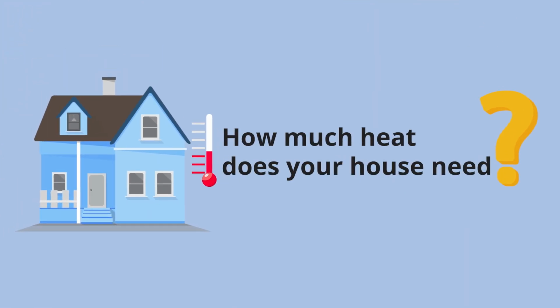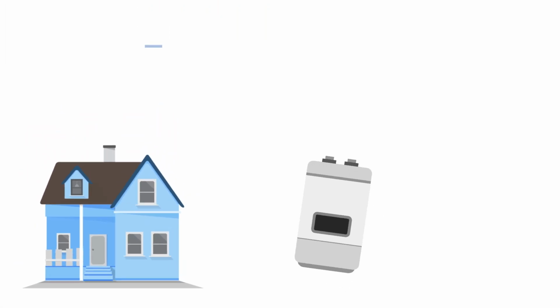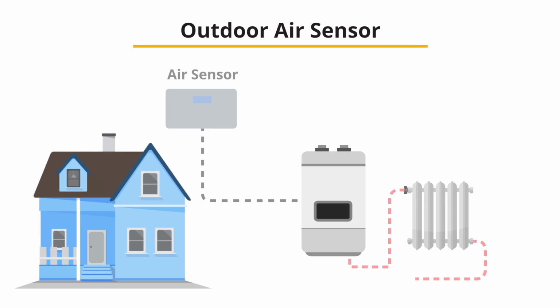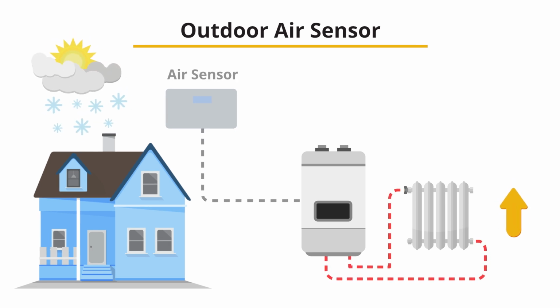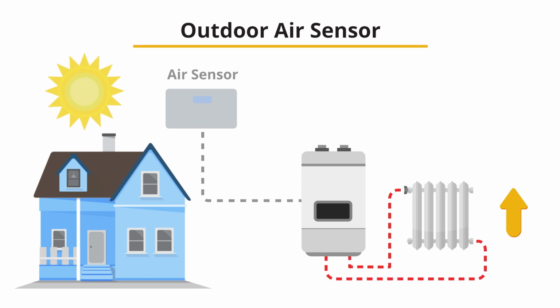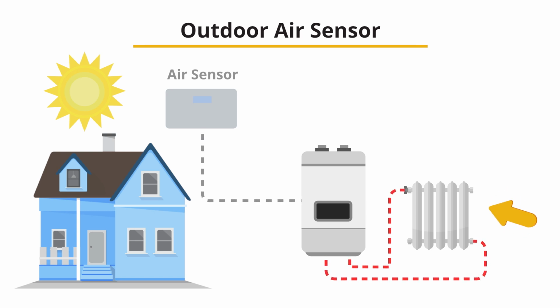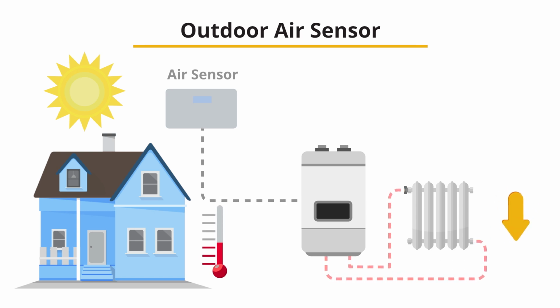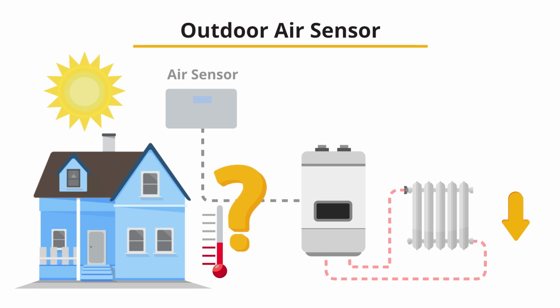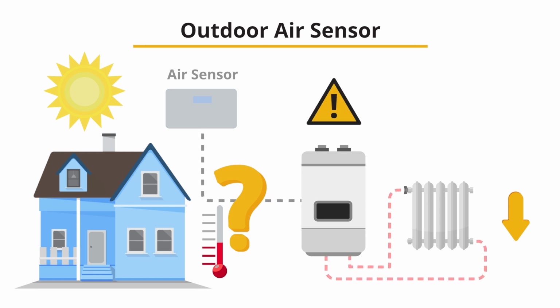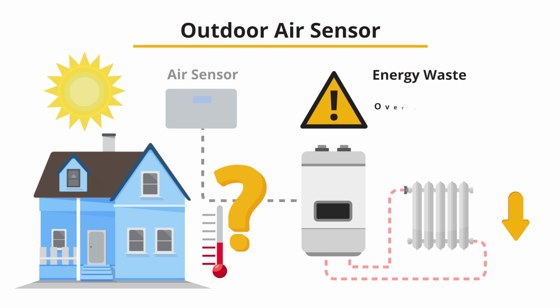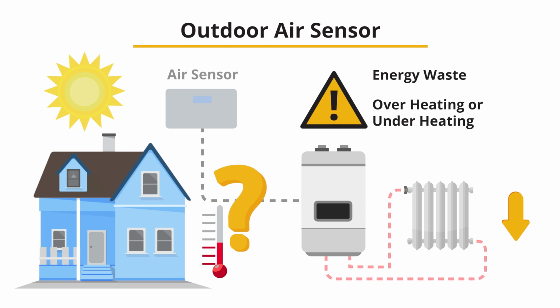The results you get from your boiler largely depend on how much heat your house needs. Most boiler companies use an outdoor air sensor to make these calculations. On colder days, the outdoor air sensor tells the boiler to increase the water temperature going out to your home. On milder days, the outdoor air sensor will reduce the water temperature. The problem is the outdoor air sensor only knows what's happening outside. It doesn't know how much or how little heat your house requires. This method may cause your boiler to work harder than it has to, wasting energy, or to not work hard enough when you really need it.